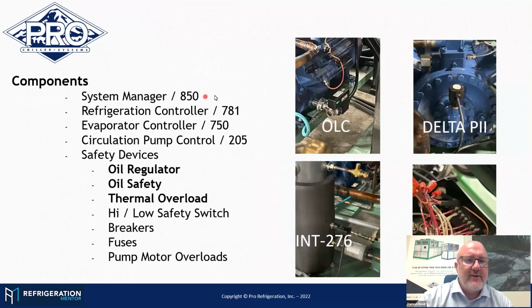So on the controls, the other items I wanted to talk about were the safety devices in the system. We've got the refrigeration controls identified, the evaporator control, and the circulation pump control. But what about the other safety devices in the system that could open from a failure condition and require troubleshooting? Just because the controller is saying, hey, my compressor's off on a safety relay, well, what is feeding that safety relay?